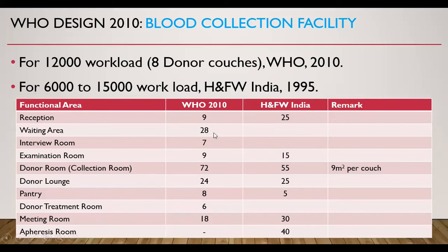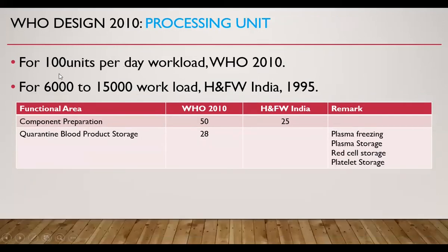For the Donor Room, the requirement is 9 square meters per donor couch, and there is a requirement of 8 donor couches for this workload. For the Processing Unit for 100 units per day workload, the subdivisions are component preparation and quarantine blood product storage. Quarantine blood product storage — including plasma, freezing plasma storage, red cell storage, and platelet storage — requires 28 square meters. Component preparation requires 50 square meters.